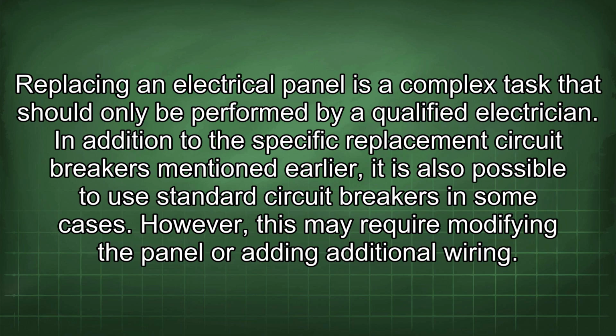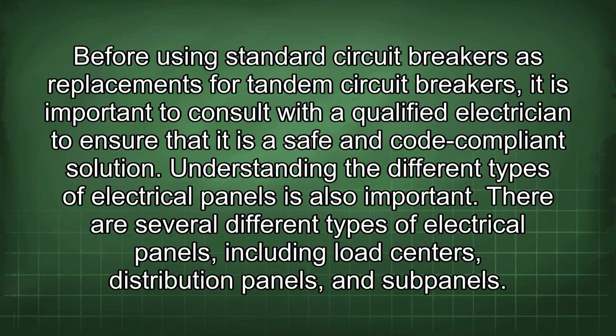In addition to the specific replacement circuit breakers mentioned earlier, it is also possible to use standard circuit breakers in some cases. However, this may require modifying the panel or adding additional wiring. Before using standard circuit breakers as replacements for tandem circuit breakers, it is important to consult with a qualified electrician to ensure that it is a safe and code-compliant solution.